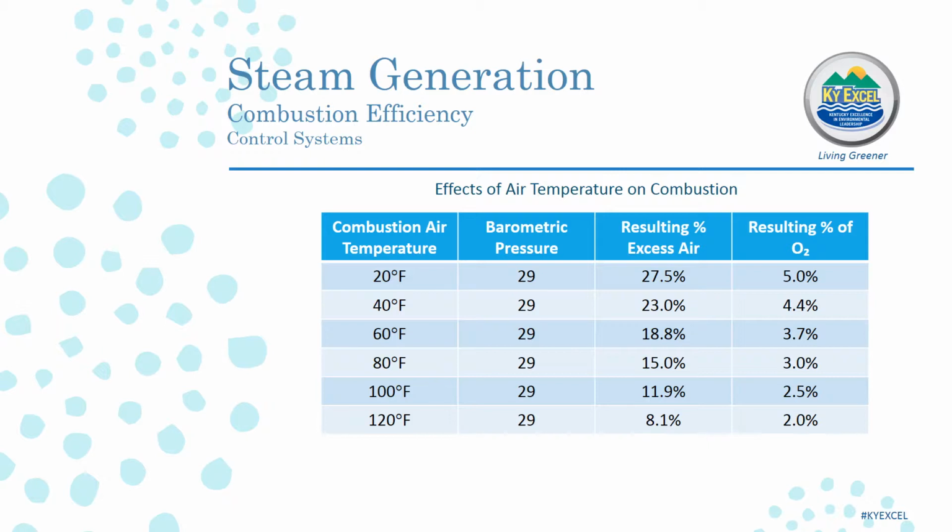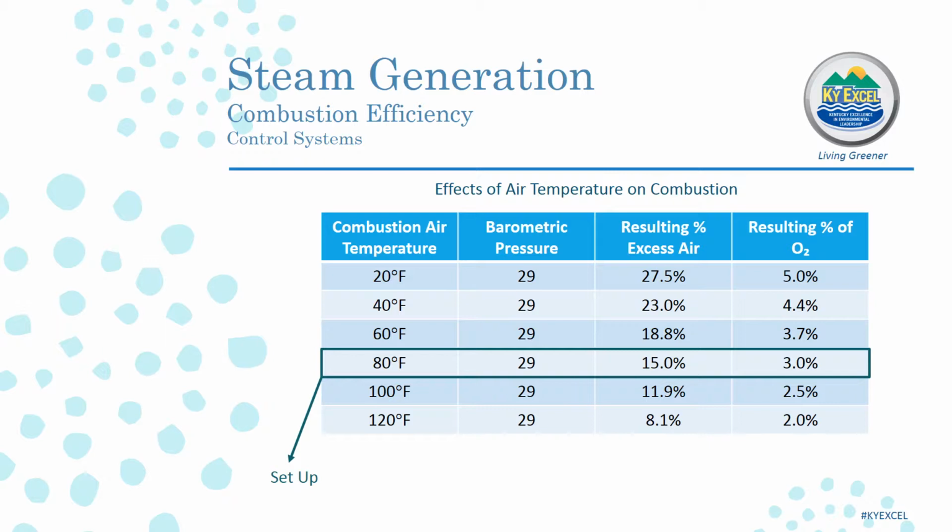For example, air temperature can affect combustion efficiency in air requirements. As air temperature drops, air density increases, and vice versa. Air density can adversely affect the excess air on a burner. Therefore, constant monitoring is recommended.